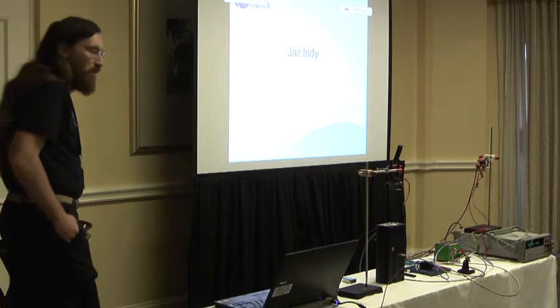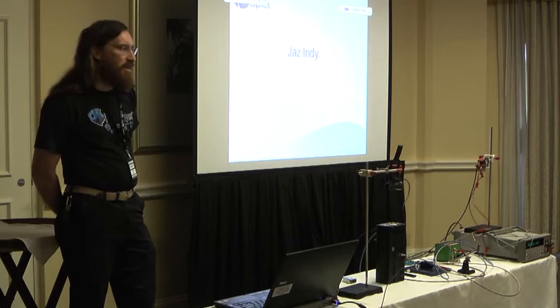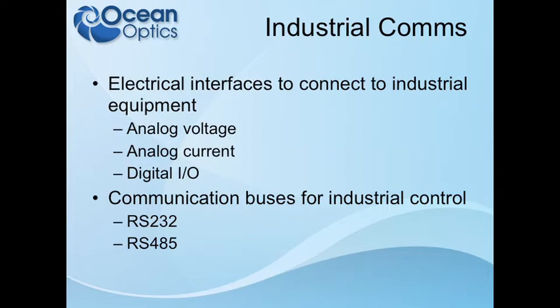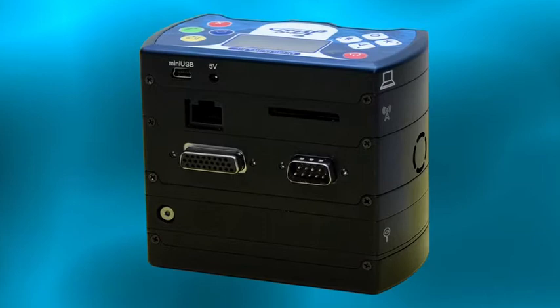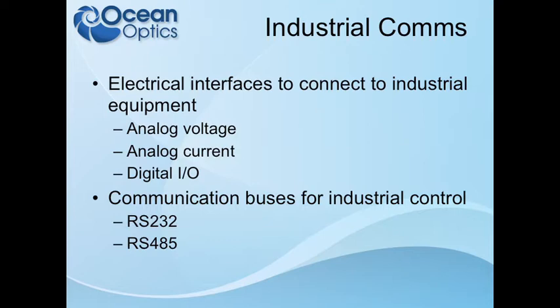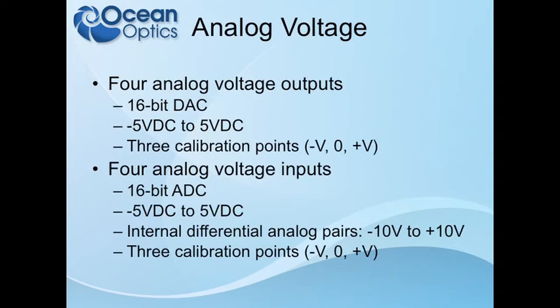We are doing a feedback control system based on spectral data with the Indy to keep this whole system at a constant level of intensity. Jaz Indy is called the Indy because it is for industrial communications — it's really to allow the Jaz to integrate with all sorts of different systems using pretty common signaling. There are two connectors on the back of the Indy: a 26-pin connector and a little 9-pin connector that has RS-232 and RS-485.